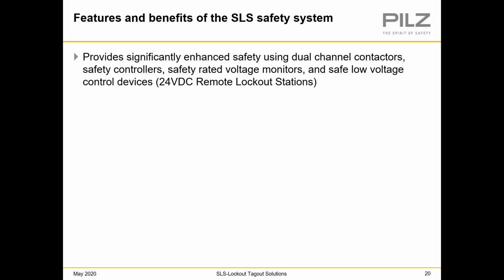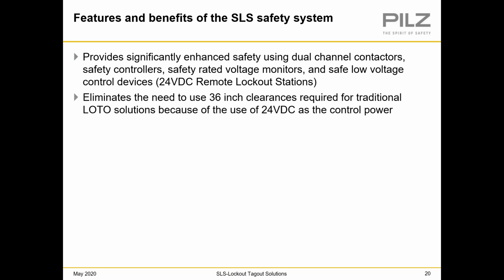So in summary, here are the benefits of the SLS system compared to traditional lockout. It provides significantly enhanced safety using dual channel contactors, safety controllers, safety rated voltage monitors, and safe low voltage control devices, 24 volts DC remote lockout stations. It eliminates the need to use 36-inch clearances required for a traditional lockout because the use of 24 volts DC is the control power, which is low enough to not be harmful.